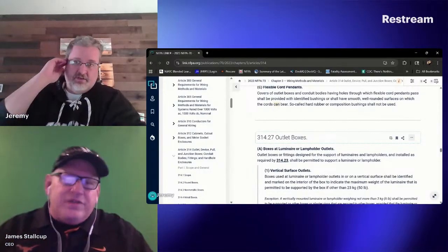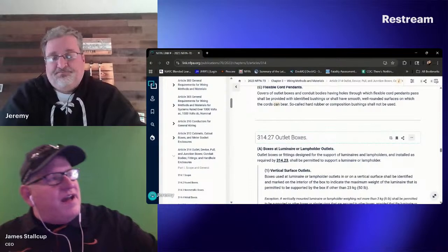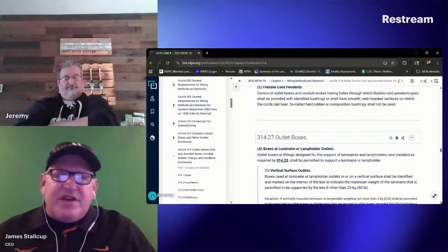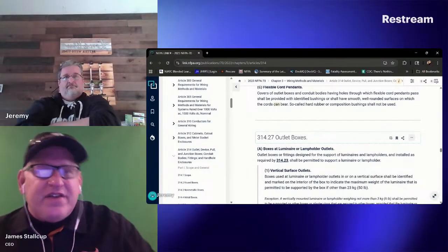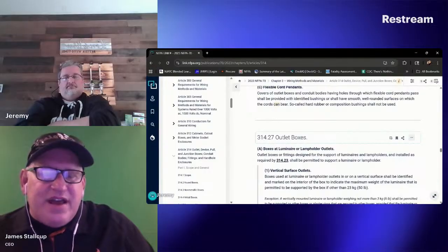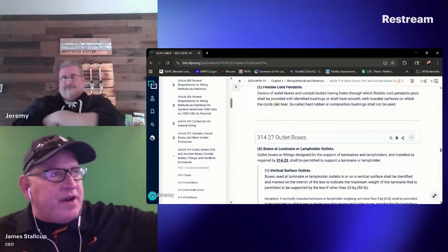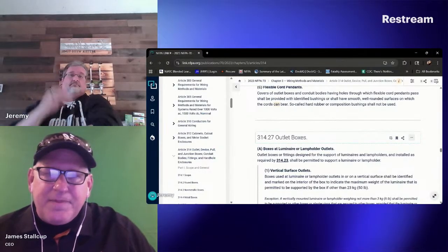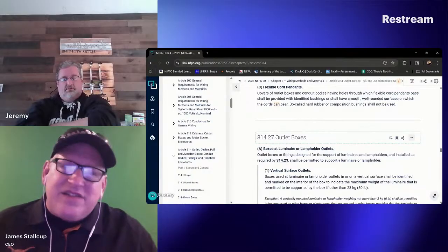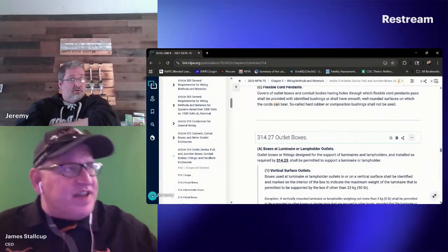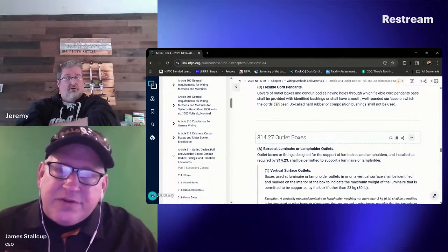See, this is why y'all don't know what you're doing. Let me ask you this. If I'm sizing the branch circuit conductors over there, how do I size those conductors going over? Now, don't forget, this branch circuit could be feeding other things. I go look at 210.19(A)(1), and if they're continuous loads, whatever, non-continuous, I size it based on there. That's the branch circuit that's coming over feeding all of that. Now, when I leave at this point, those are not branch circuit conductors, because I could be coming up with number 14, but I fed everything over here on the branch circuit with number 12s.